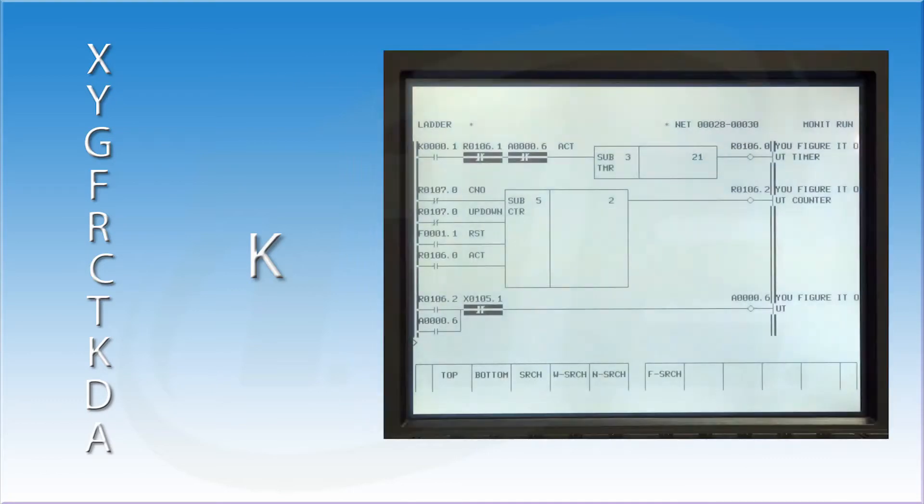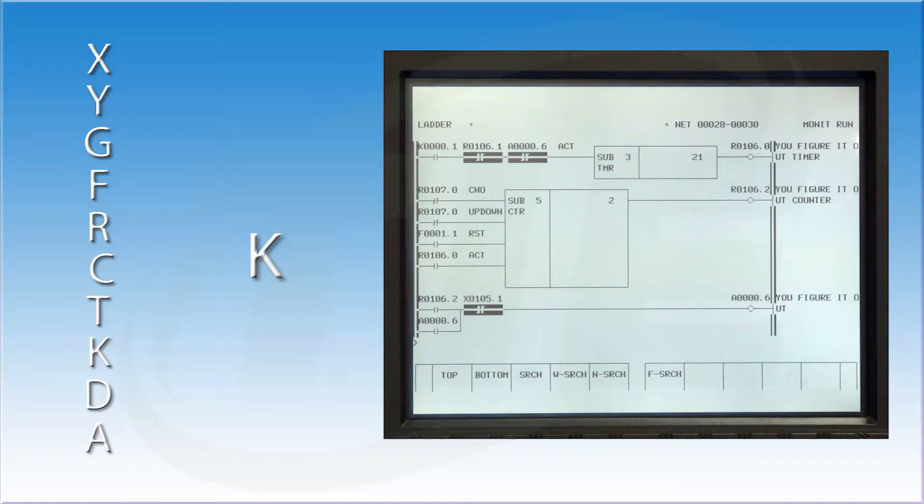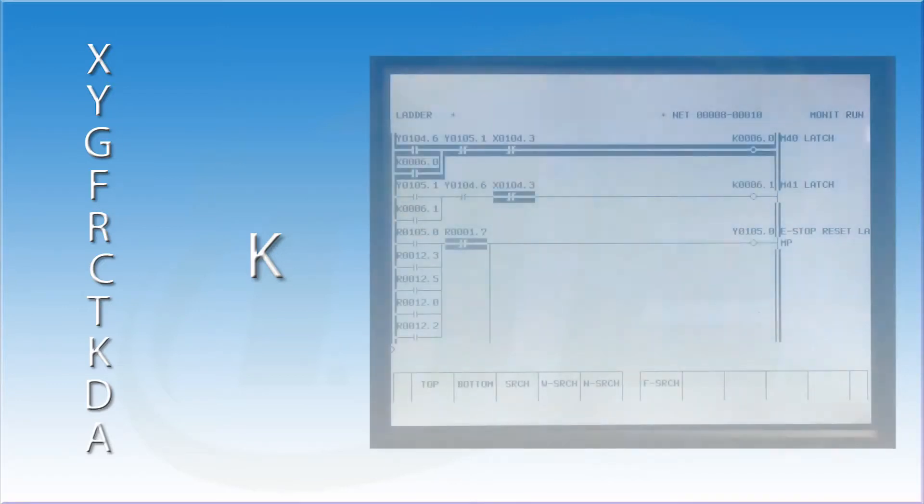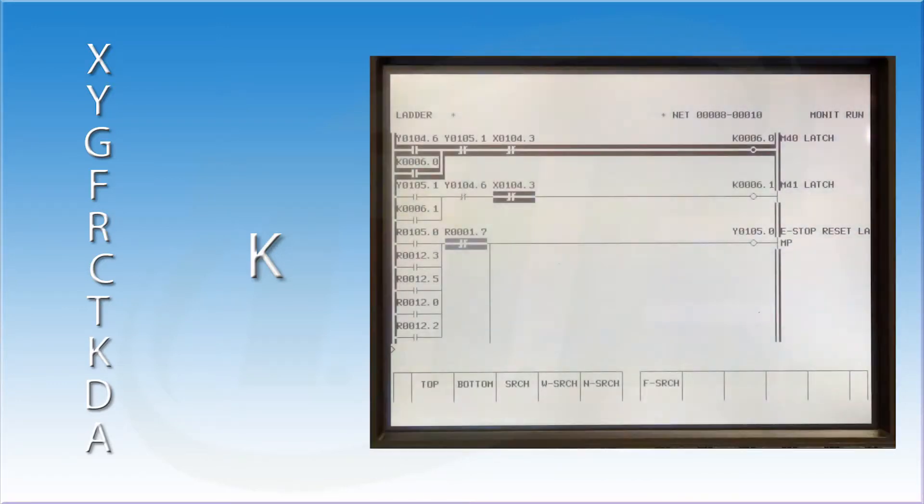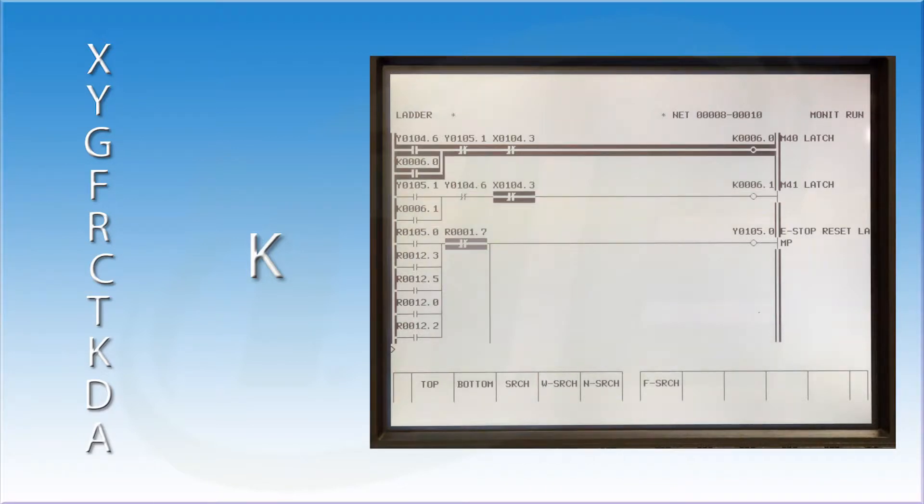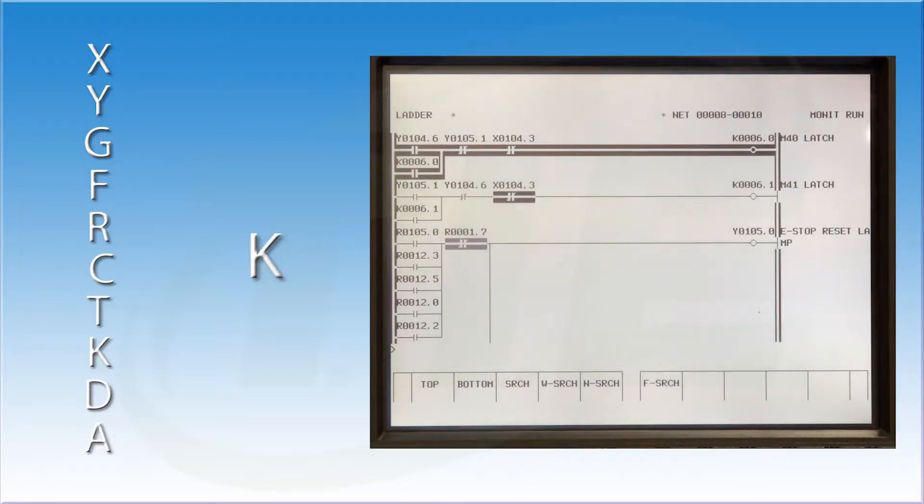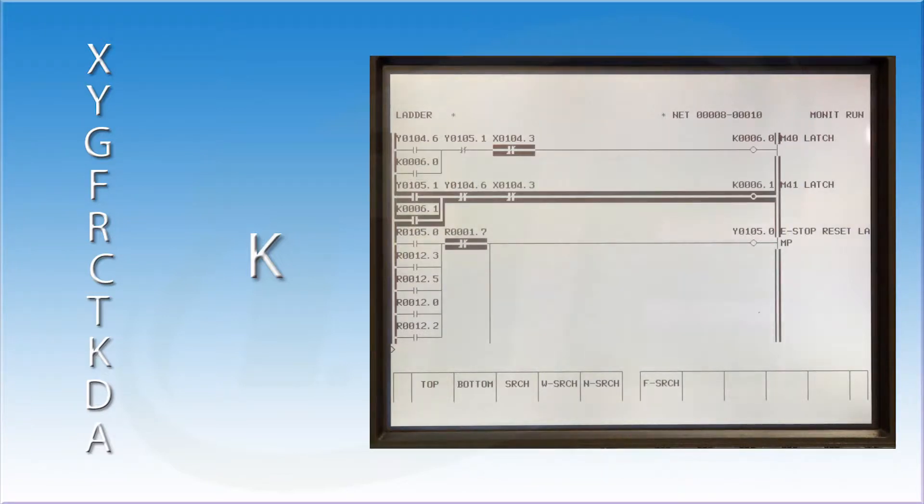The keep relays can also be used to enable or disable certain functions in a ladder logic, such as automatic doors, index tables, or robot interface. Typically, a machine tool builder will write one ladder for a machine model. Not all machines are sold with all options. The machine tool builder will use the keep relays to enable the options that a customer purchased. Keep relays can be used as contacts or coils in the ladder. Some builders use them to retain the status of certain events. Since the last state of the keep relay is retained in memory, it can be used to record information, such as what pallet was in the machine when it was shut down, or the clamp unclamp status of a chuck.